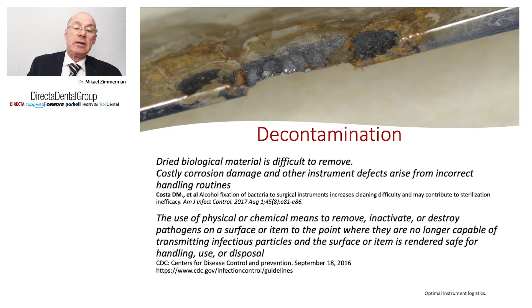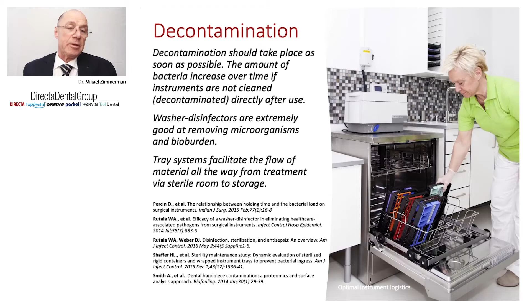The most effective decontamination should always take place as soon as possible after the treatment. The amount of bacteria will increase over time if instruments are not cleaned and decontaminated directly after use. There is also a risk of several products that could cause corrosion on our instruments and destroy the instrument surfaces, making them less delicate to work with. Today, washer disinfectors are extremely good at removing microorganisms and bioburden. And by having a tray system, you will facilitate the flow of material all the way from treatment via the sterile room to storage.